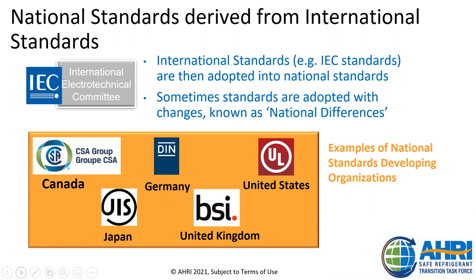So, by the way, UL here doesn't mean the UL certification and testing agency, which is the more popularly known agency, but the UL Standards Division, which is accredited by ANSI. So the safety standards for air conditioning and heat pumps are actually ANSI standards. It is parallel to how some other organizations work as well. In fact, CSA is similar. They have a certification listing agency, but they also write Canadian national standards. And AHRI is another one that certifies performance of equipment, but they also write their own standards and are ANSI accredited. So you will also find parallels in other countries and other industries, such as UK, Germany, Japan, as they're listed here on the slide. Next slide.